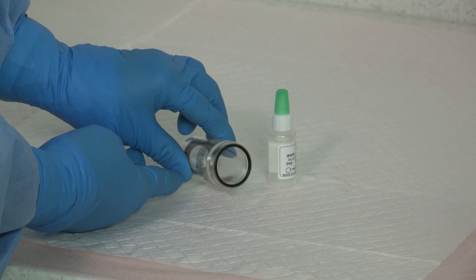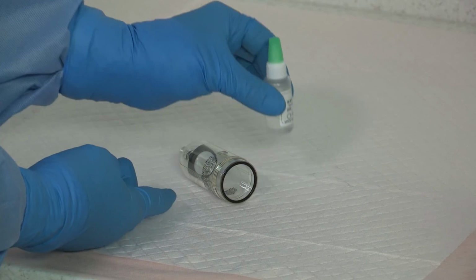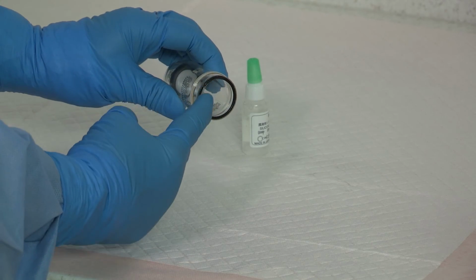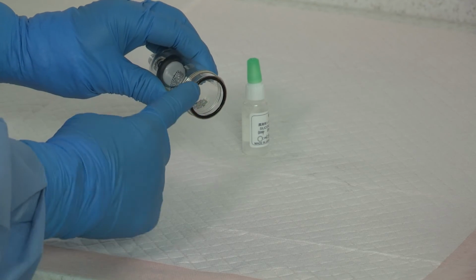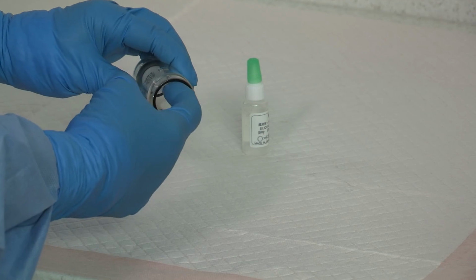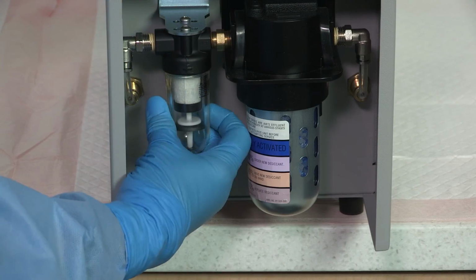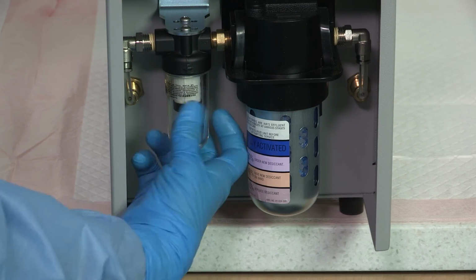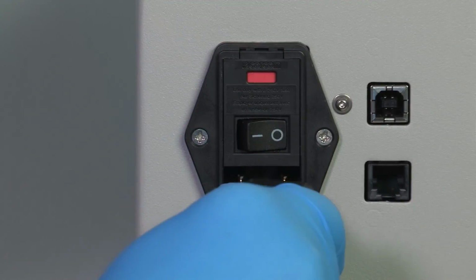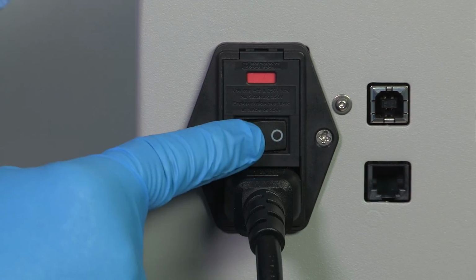Examine the clear plastic bowl and ensure the O-ring is seated in the groove on top. If the O-ring is dry, add a small amount of silicone oil to ensure a good seal. Replace the clear plastic bowl by twisting it back into the filter housing until tight. Plug in the unit and turn the system power on.